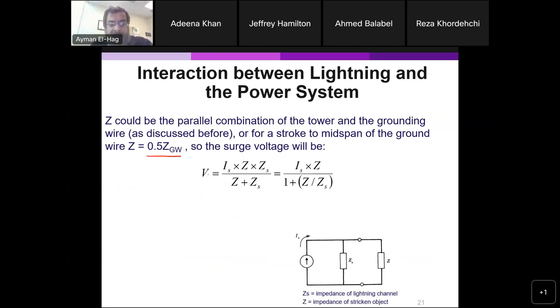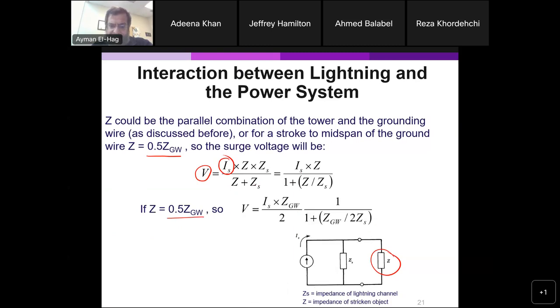So the voltage that you will have is equal to the surge current times the parallel combination of Z, which could be 0.5 as we have it in this case, or it could be the tower in parallel with your ground wire. Okay, so simple calculations here. Divide by ZS on both sides, so we get this formula. This is your voltage. Now, if Z is equal to 0.5 the ground wire, just replace it with this.